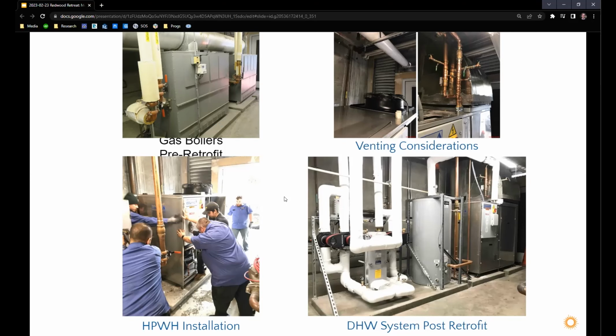One challenge we had with this project was that after installation, we got noise complaints, where the amount of noise ejected from inside this room, out of this louver, was actually causing people in the street to complain. It turned out this unit was producing 85 decibels measured outside on the street.